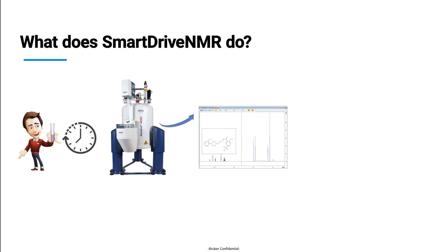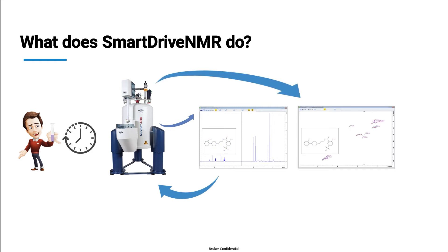This Proton is analyzed and, if time allows, follow-up experiments are proposed. The follow-ups are carried out with optimized parameters in full automation — in this case, a 2D experiment. This is the whole concept of Smart Drive NMR: the core is a self-driving spectrometer delivering high-quality NMR spectra.